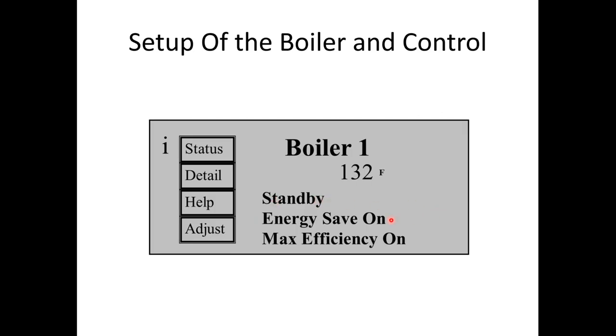Energy save on will only show up if you're using the outdoor sensor. The unit comes looking for the outdoor sensor. Max efficiency on will come and go. It only shows up when we have return water temperatures of 130 degrees or lower, when the boiler is going to be condensing. And while we're right here, I'm going to pause for a second and show a video of how to do the central heat setup.